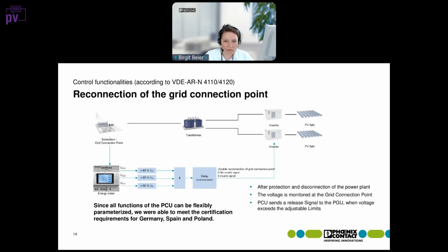There we have a power plant again with a PV field. After a protection and disconnection of the power plant has happened, the voltage is monitored by the energy meter at the grid connection point. Then the PCU sends a release signal to the PGU, the power generation unit, when the voltage exceeds the adjustable limits. Those limits are here about 85% on all 3 phases.